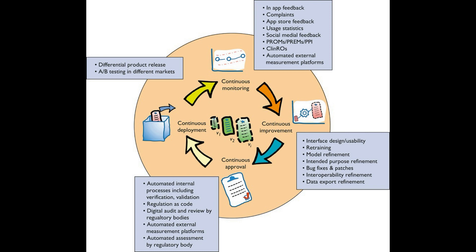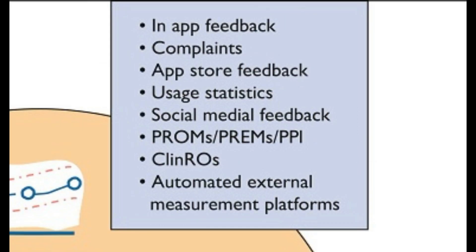I'm going to talk through this figure starting from the top, which shows a plot of a graph of trend reporting of the performance of an application in a figurative sense, titled 'Continuous Monitoring.' The concept of continuous monitoring is that when a digital health application is released on the market, the manufacturer can carry out assessments on that application with users throughout its time of use on the market. This is required in world markets and is often known as post-market surveillance. The manufacturer can use a variety of approaches to gather data, one of which is in-application feedback from users.